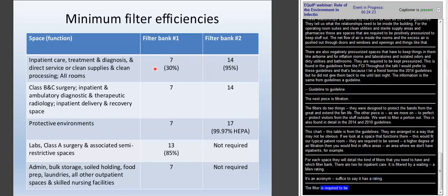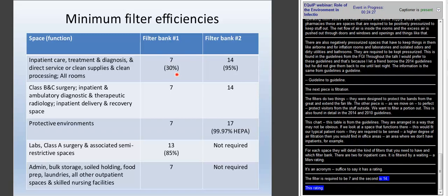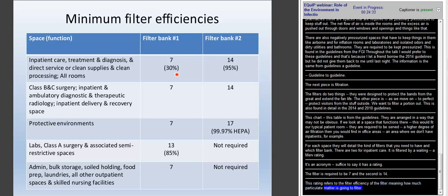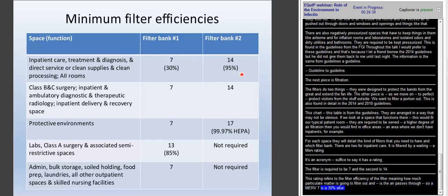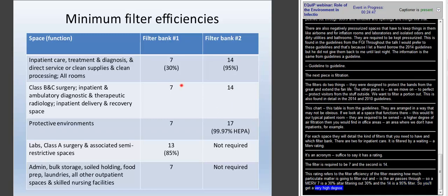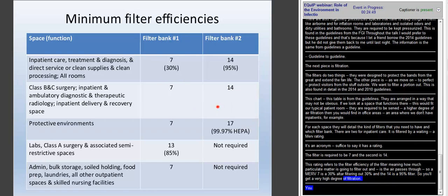This rating refers to the filter efficiency of that filter, meaning how much particulate matter it's going to filter out as the air passes through it. So a MERV 7 filter is a 30% filter, which will filter out 30% of the dust, and a MERV 14 is a 95% filter. So you'll get a very, very high degree of filtration. You get the same level of filtration for Class B and C surgery areas, inpatient diagnostics, and so forth. It's a high level of filtration.